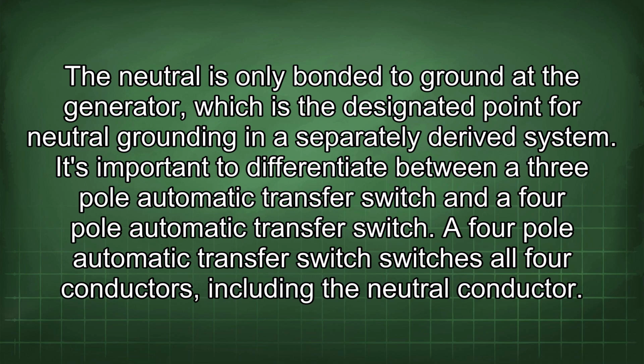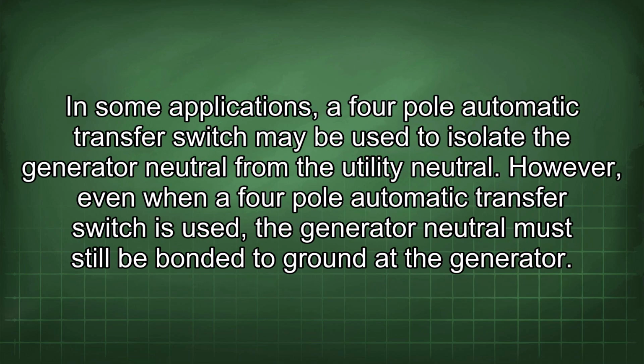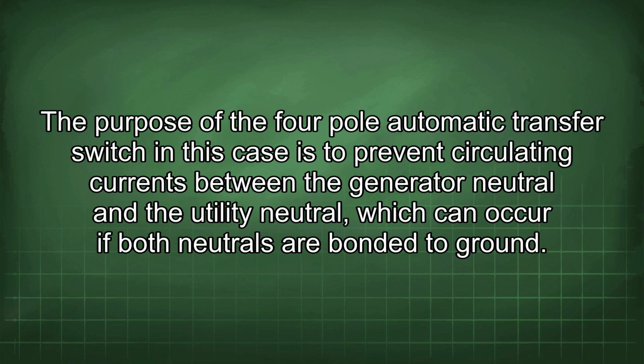It's important to differentiate between a 3-pole automatic transfer switch and a 4-pole automatic transfer switch. A 4-pole automatic transfer switch switches all 4 conductors, including the neutral conductor. In some applications, a 4-pole automatic transfer switch may be used to isolate the generator neutral from the utility neutral. However, even when a 4-pole automatic transfer switch is used, the generator neutral must still be bonded to ground at the generator. The purpose of the 4-pole automatic transfer switch in this case is to prevent circulating currents between the generator neutral and the utility neutral, which can occur if both neutrals are bonded to ground.